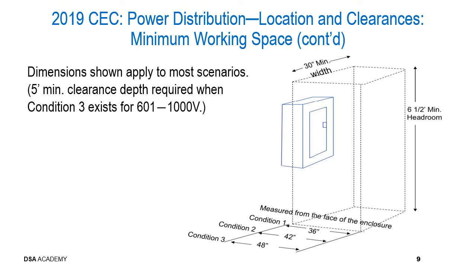This sketch right here is an attempt to provide a very simple visual representation of the different conditions that we just discussed and also the dimensions that we also discussed. And as you can see by looking at this, there's a 30-inch minimum width, a 6 foot 6-inch minimum height requirement, and depending on which condition it is, either 36 inches, 42 inches, or 48 inches in depth is generally required.